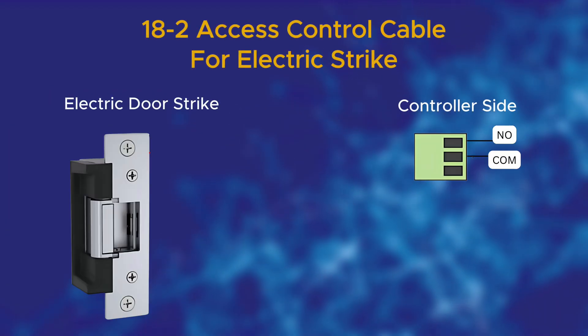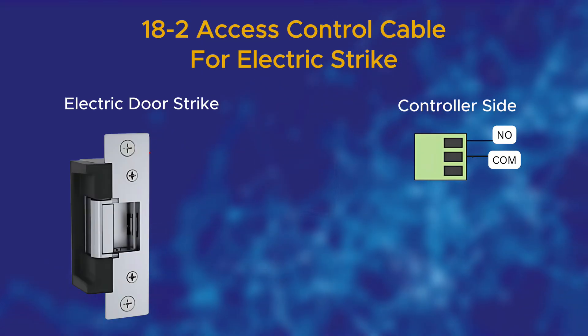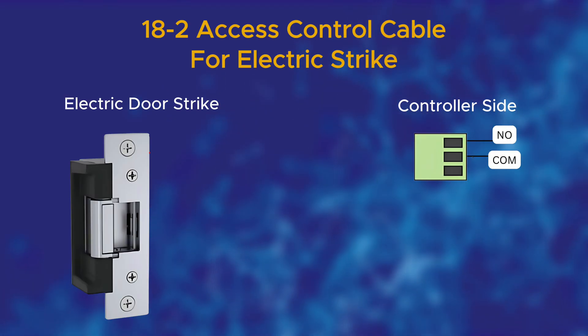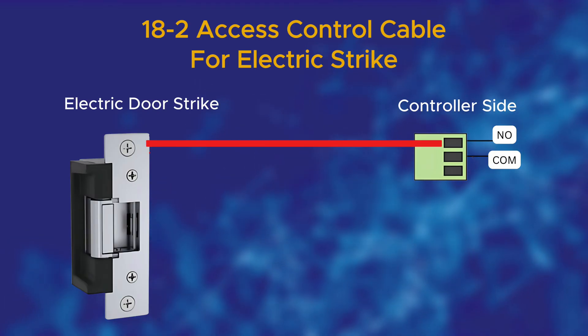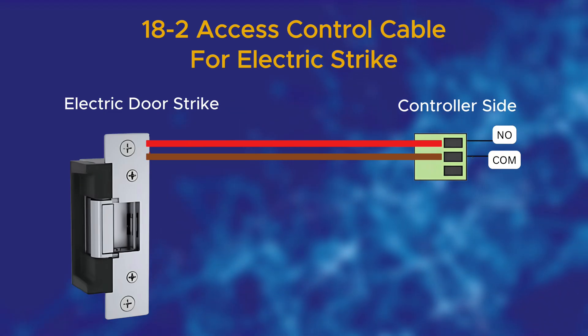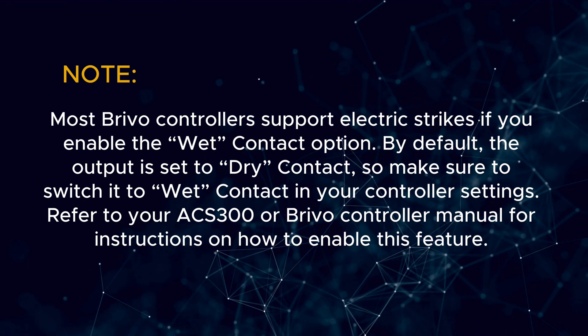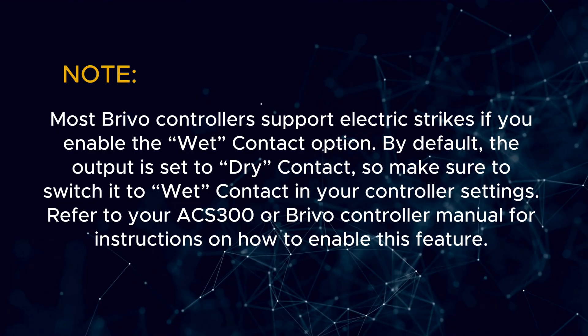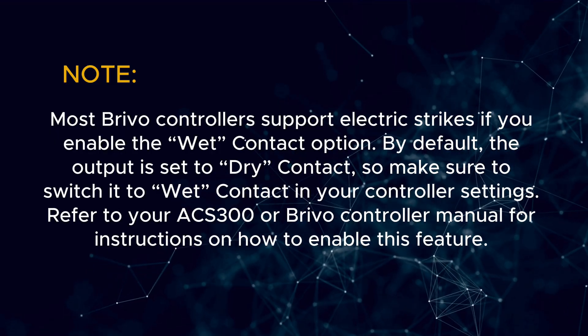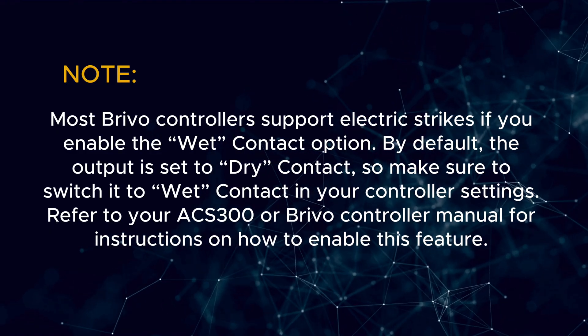In this next diagram, I'll show you how to wire an electric strike or door strike using 18-2 cable from the door side back to the controller. At the door, the electric strike will have two wires, typically brown and red. Connect the red wire to the NO — normally open — terminal on the controller, and connect the brown wire to the COM, common terminal. Most Brivo controllers support electric strikes if you enable the wet contact option. By default, the output is set to dry contact, so make sure to switch it to wet contact in your controller settings. Refer to your ACS300 or Brivo controller manual for instructions on how to enable this feature.